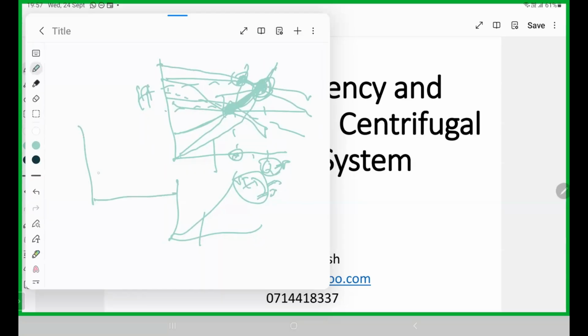This is the system. Always you have to keep the system in mind. If the diameter is less, or higher, the system curve is this one, and then your head requirement. Then the flow rate is this one. If you select a higher flow rate instead of a lower flow rate, my idea is that we should take at least 1 hour to fill the tank, but in most cases the pump is oversized. That is energy inefficiency in the household.